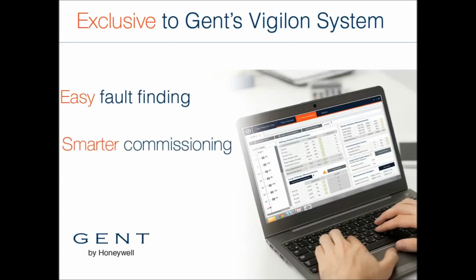While commissioning new systems, the LDT allows you to check the condition of the loop handed over to you by the installer and ensure the integrity of the commissioned loop, even at full alarm load. Use of the LDT before starting a maintenance contract can confirm any problems that may be encountered, and the built-in reports can be used to support your engineer's documentation. Now I'm going to give you a quick tour of the tool itself.